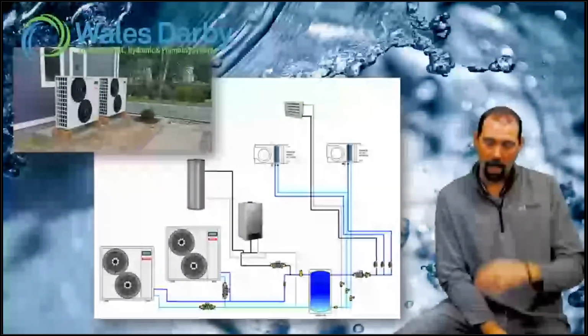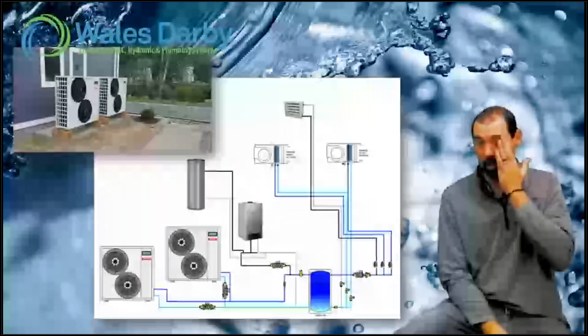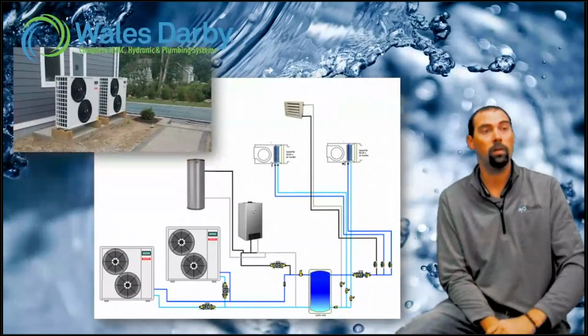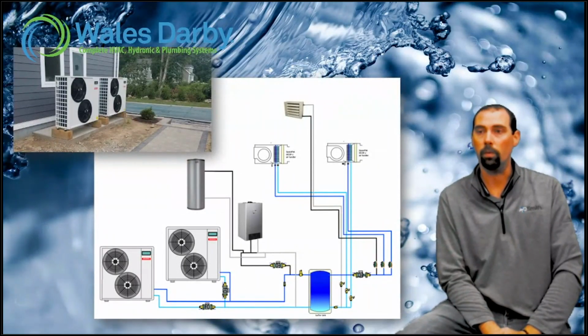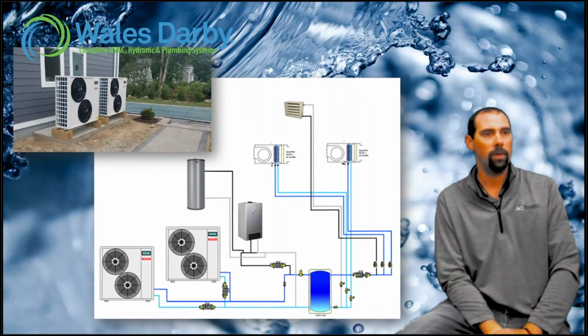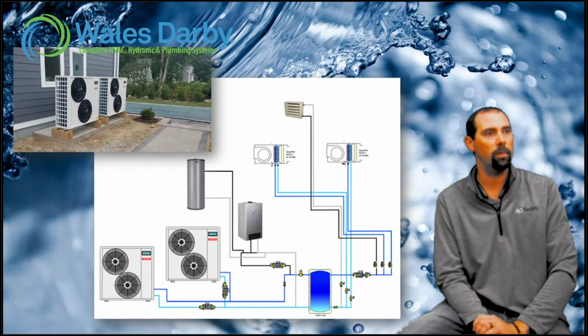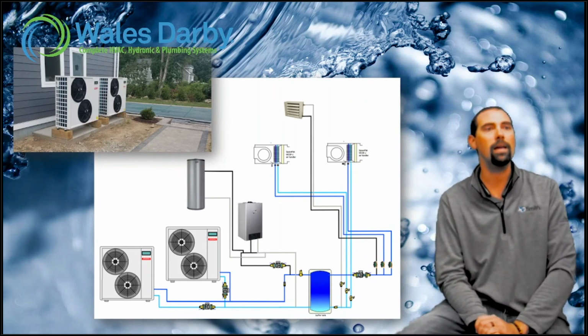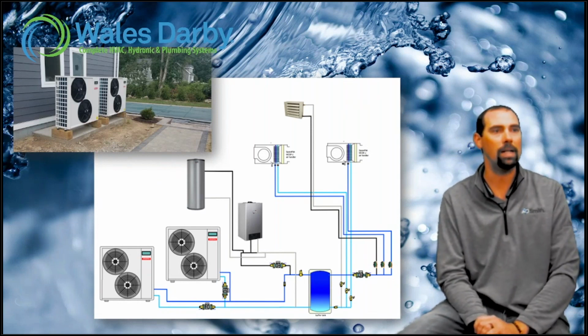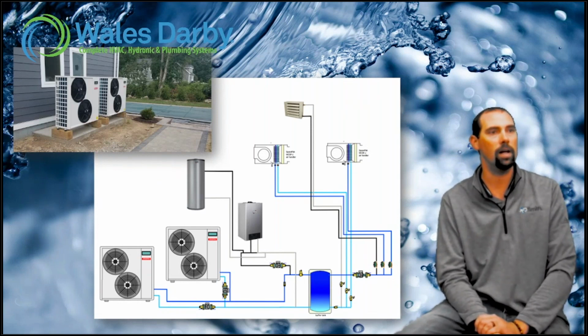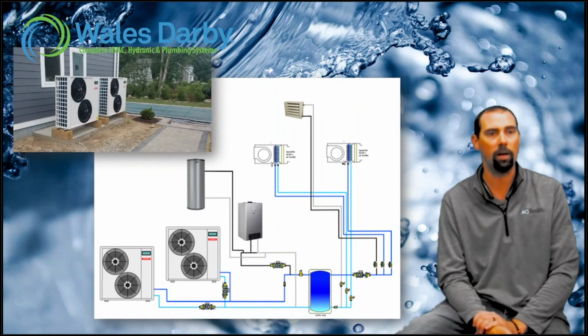I like what you said about going heavy, I hear guys say 30%, 40%, thinking about fluid freezing or burst protection and all that. But even on a 10-degree day, a 5-degree day, that's air temp, not fluid temp, the fluid isn't getting that cold. So just because you hit a couple of 10-degree days doesn't mean you need protection down to minus 22, or even 10 degrees. The glycol doesn't need to be there for that, and I think that's an adjustment SpacePak made too.